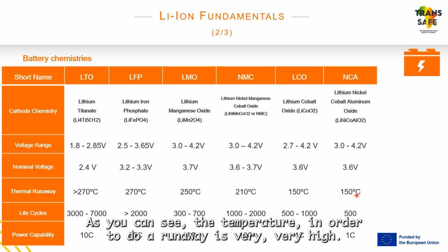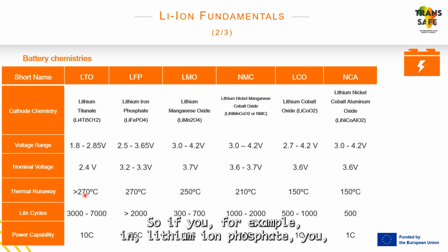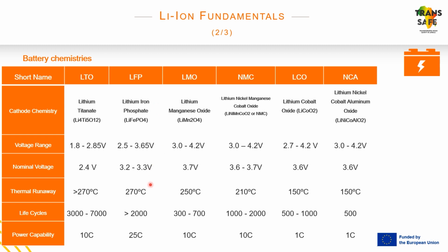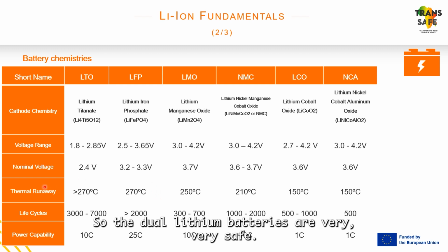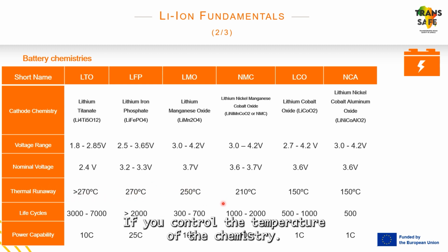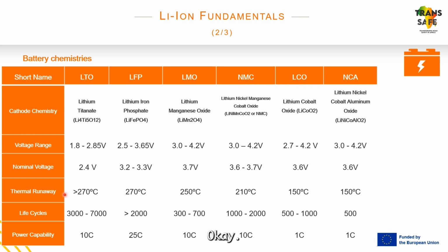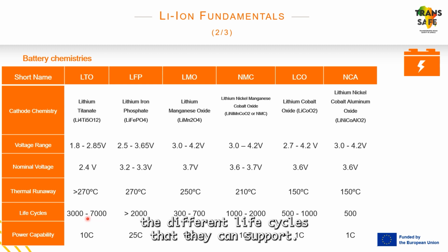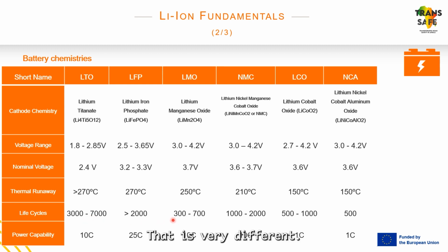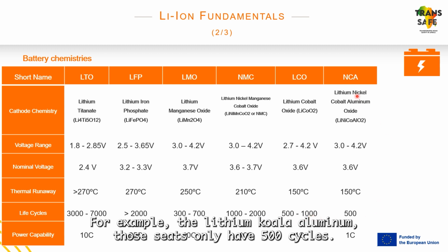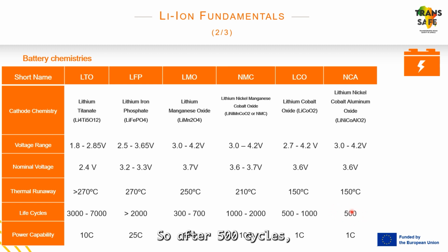The temperature needed to cause thermal runaway is very high. For example, in lithium iron phosphate you can support 270 degrees of temperature before reaching thermal runaway. So lithium-ion batteries are very safe if you control the temperature of the chemistry. You can also see the different life cycles they can support - it's very different. For example, lithium nickel cobalt aluminum oxide only has 500 cycles, so after 500 cycles the aging is going to damage the battery very hard.